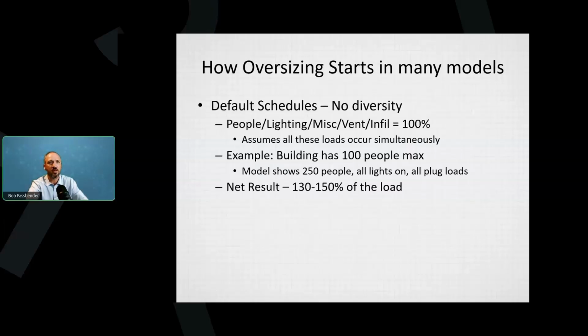Let's look at how oversizing starts, and I'll try to be 30 seconds here. Basically, it starts with you have schedules. So you put your people, lighting, miscellaneous, infiltration, ventilation, all of those things into the software, and you fill out what they are. And by default, it assumes all of those happen simultaneously. So, real simply put, a building has 100 occupants maximum. Well, your model does the math based on your schedules, and it shows there's 250 people in the building. All the lights are on and all the plug loads are on. And the result, because the envelope and the glass all stays the same, and that's factored in, but the net result is you're up 130 to 150% on your load.